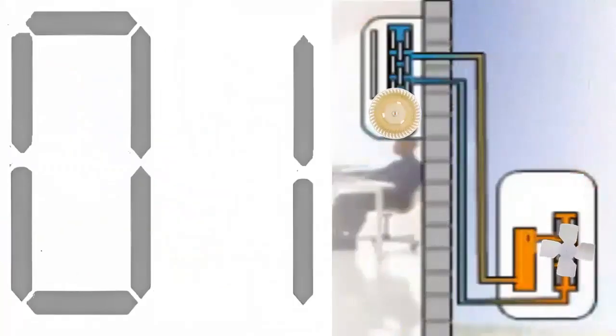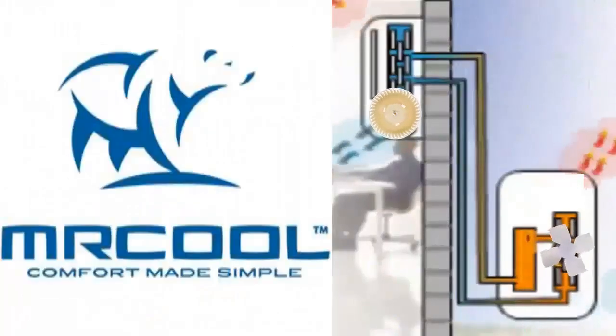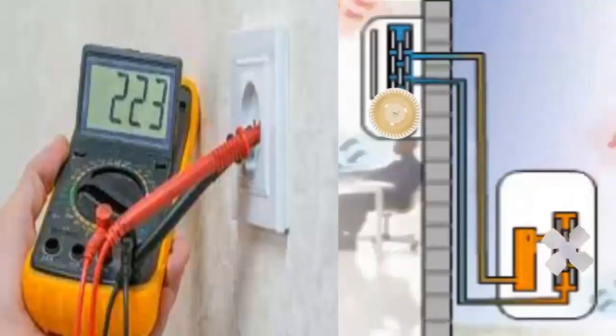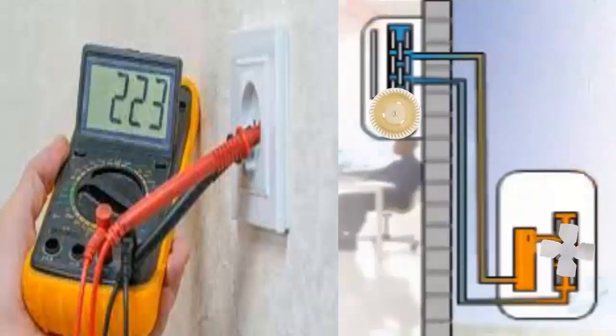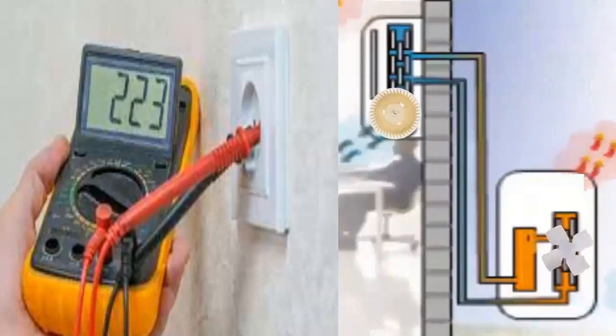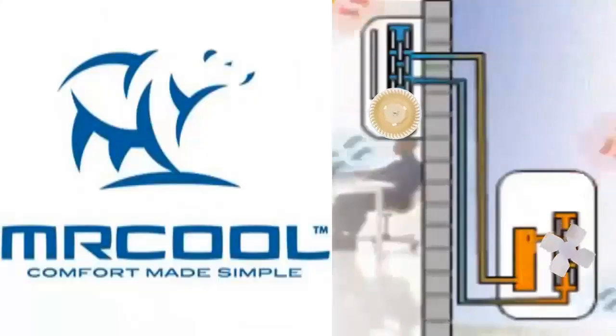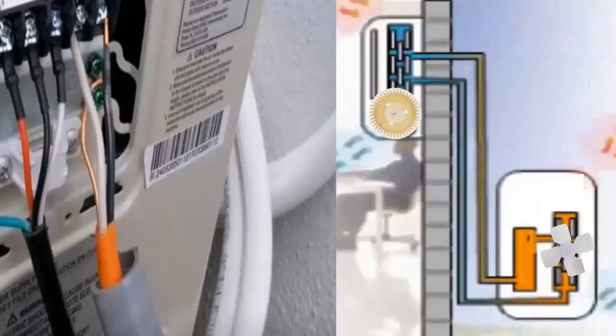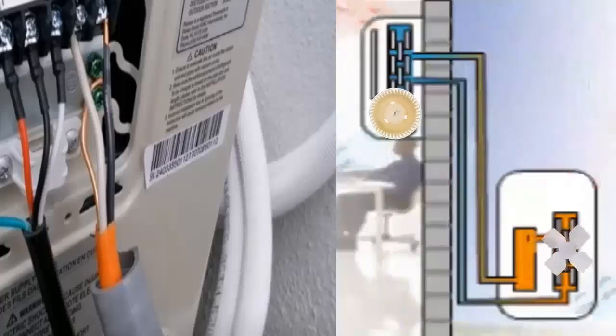2. If the error persists, measure the voltage supplied by the external power grid. If it is unstable, consider using a voltage stabilizer. 3. Perform a visual inspection of the external connections and the condition of the visible cables between the indoor and outdoor units.